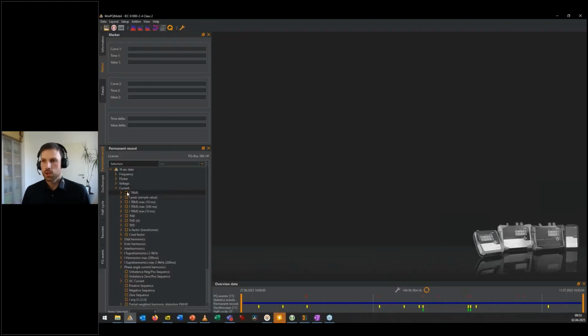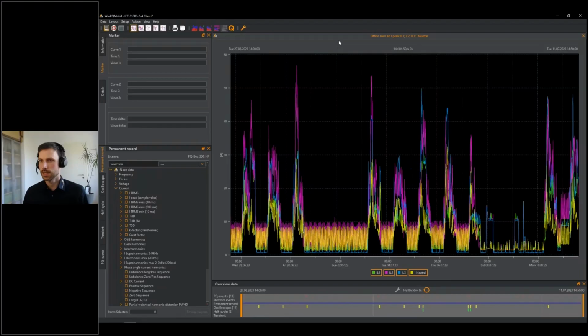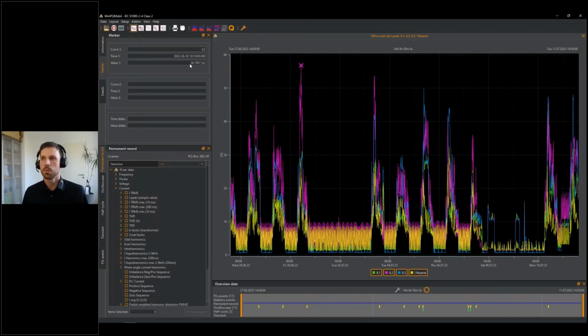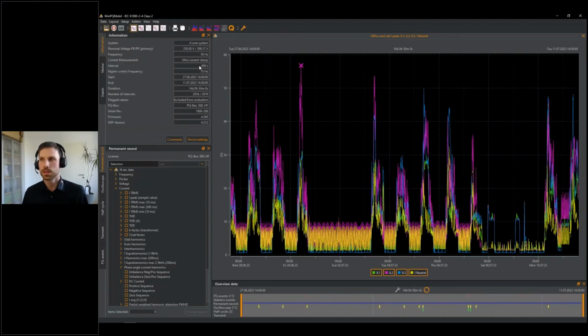So first what I'm going to check is the true RMS value of the current. I open the timing diagram, and now I see the true RMS value of the current. I see peaks. I hold down the shift key and do a left click and see peaks at around 56 amps. So please consider this is a 10-minute average value. 10-minute average values are good when it comes to the thermal condition of your conductors. If you want to see thermal overloads, they don't happen with short peaks, but if you continuously stress the conductors with values that are too high, then they get warmer and warmer and may get damaged.